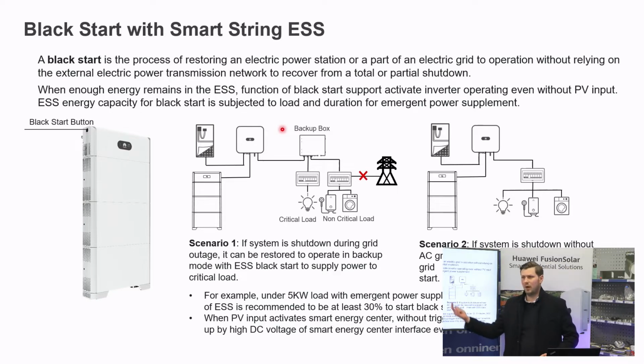We have the limited power of the inverter by maximum power. So if we have a 10 kilowatt inverter, the maximum power we can get from the backup box is 3.3 kilowatts, because it's simply 10 kilowatts divided by three phases.